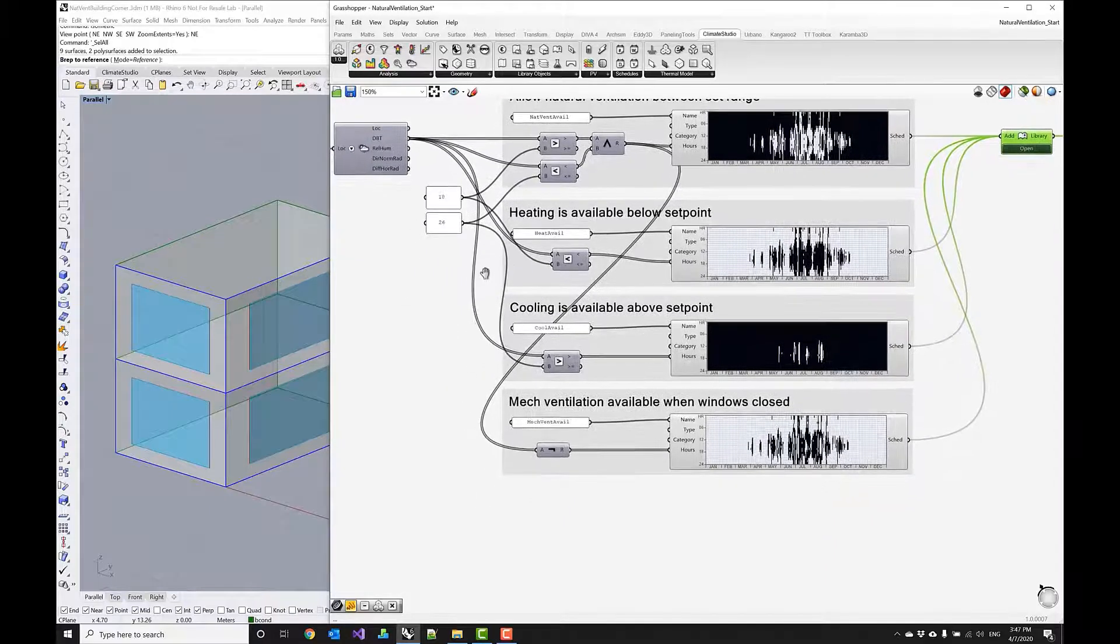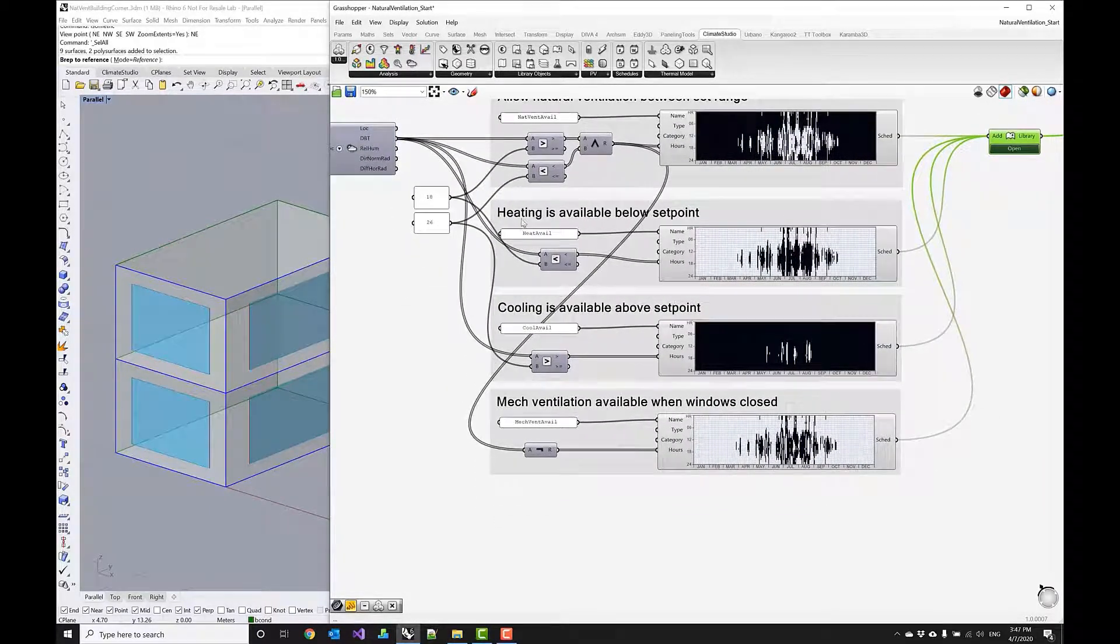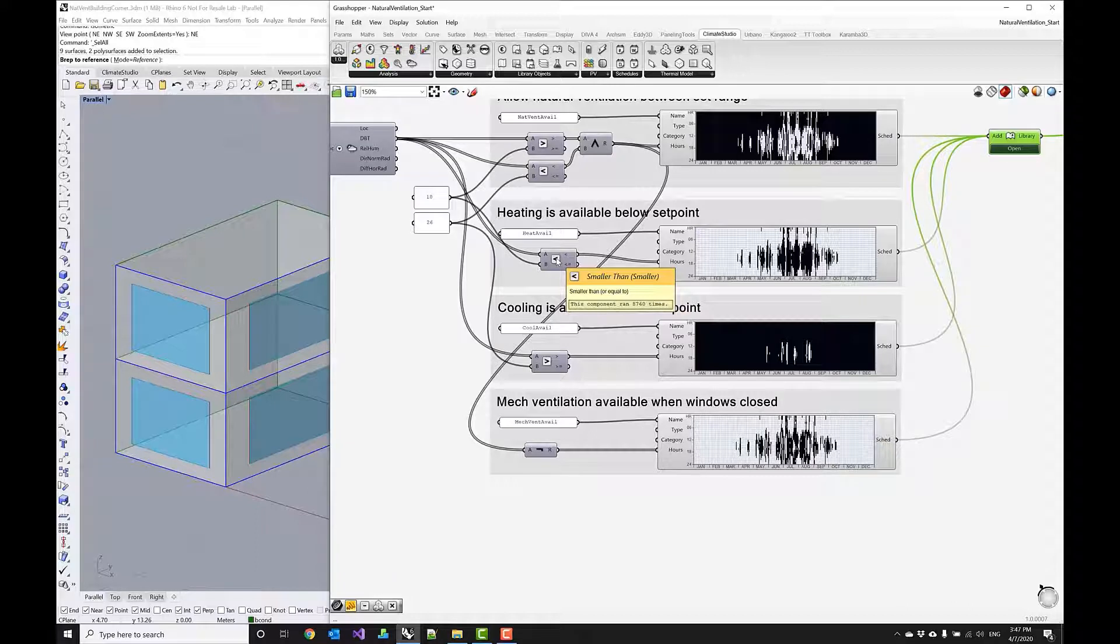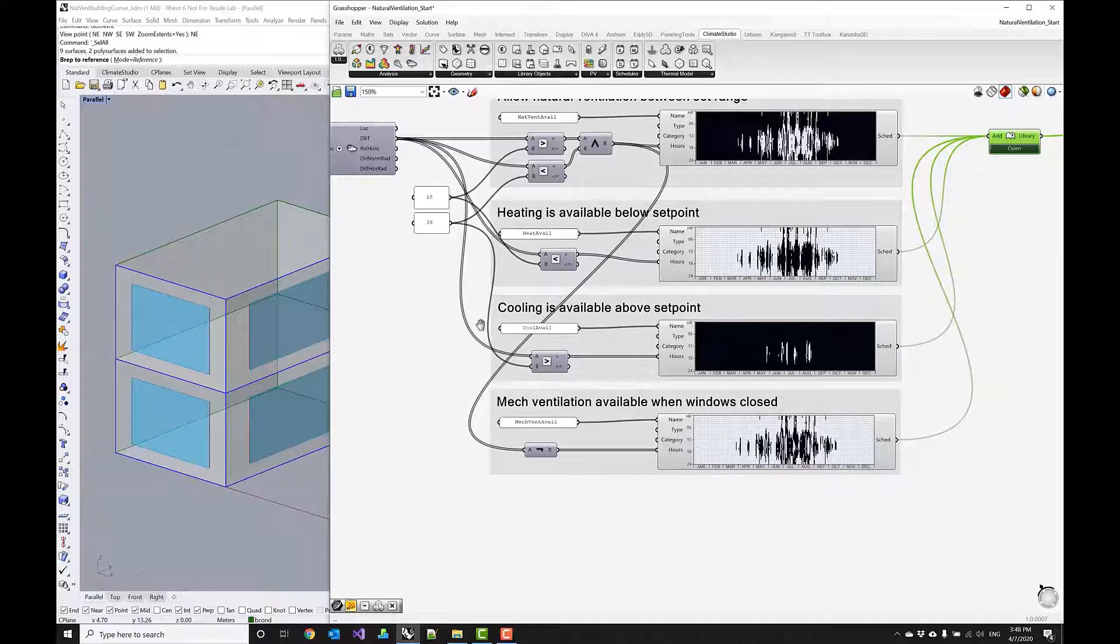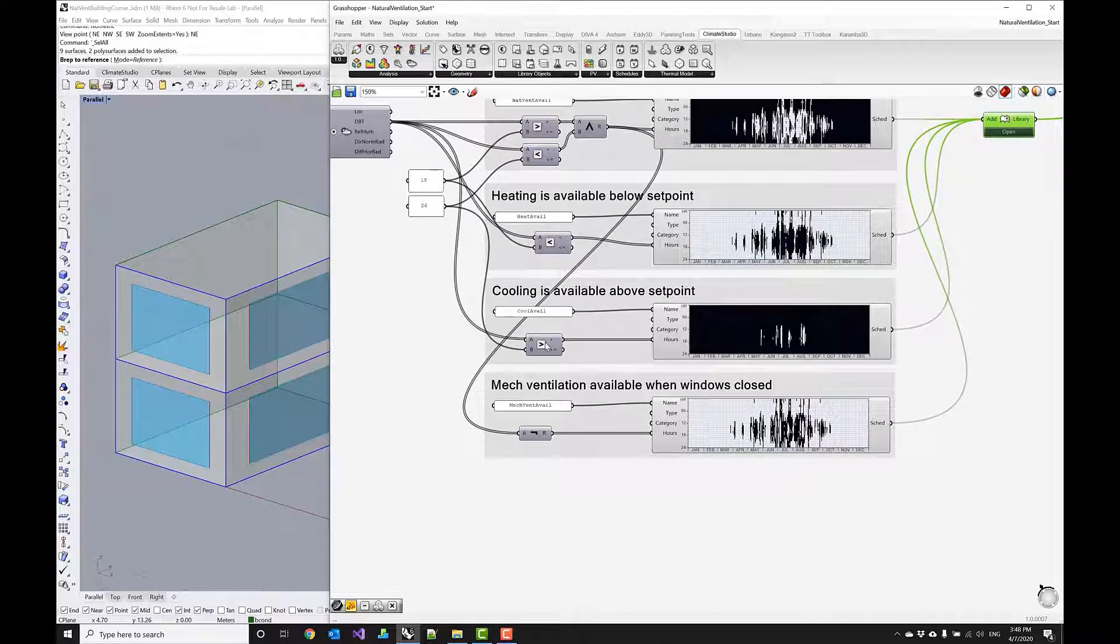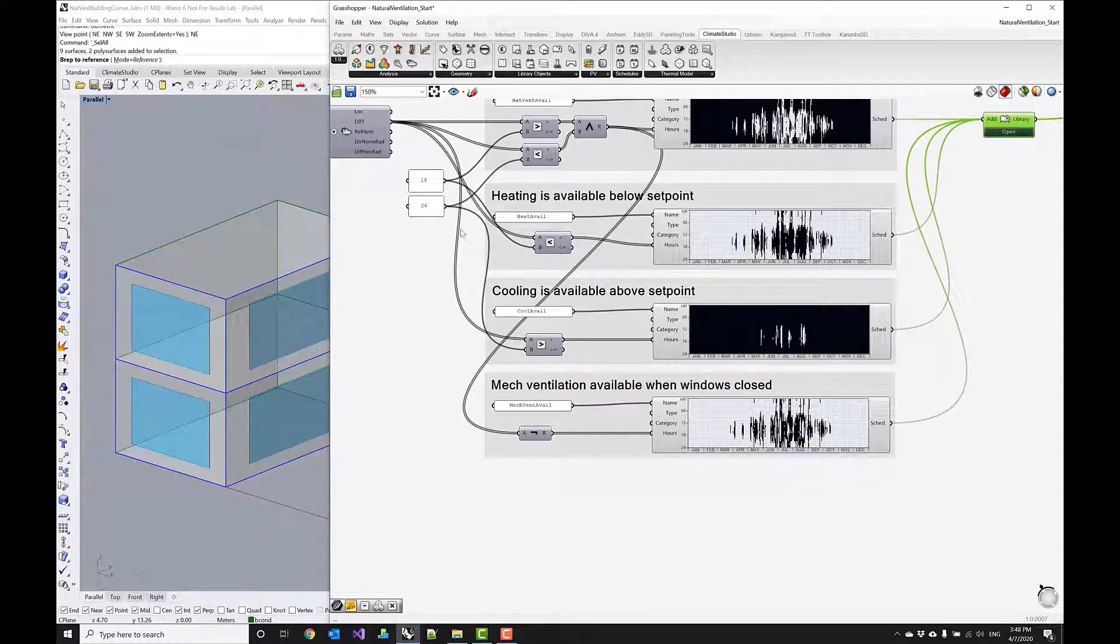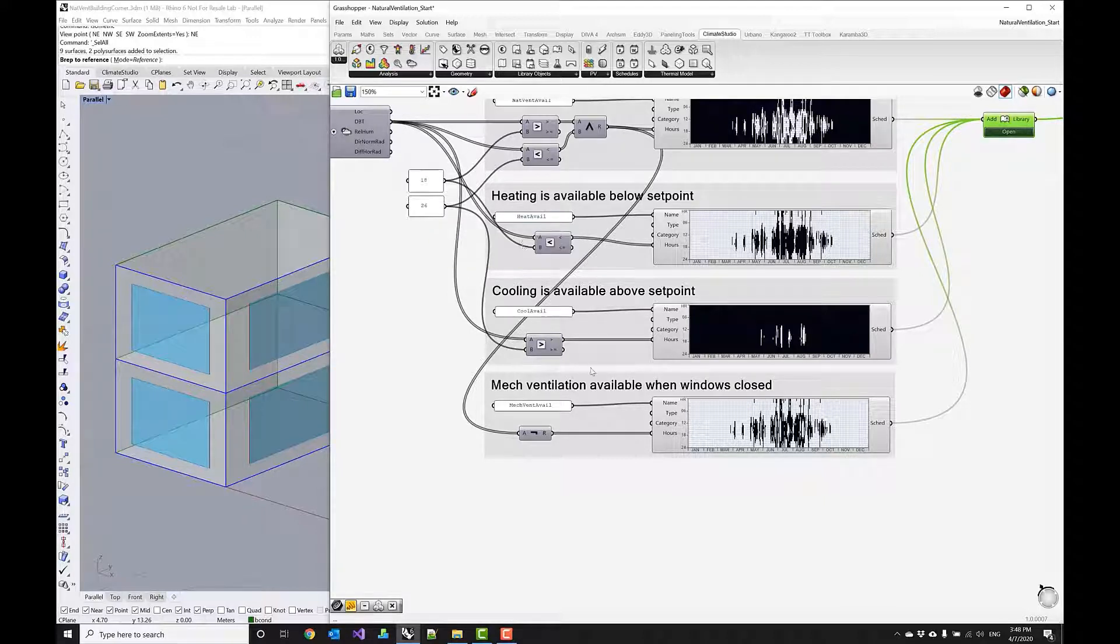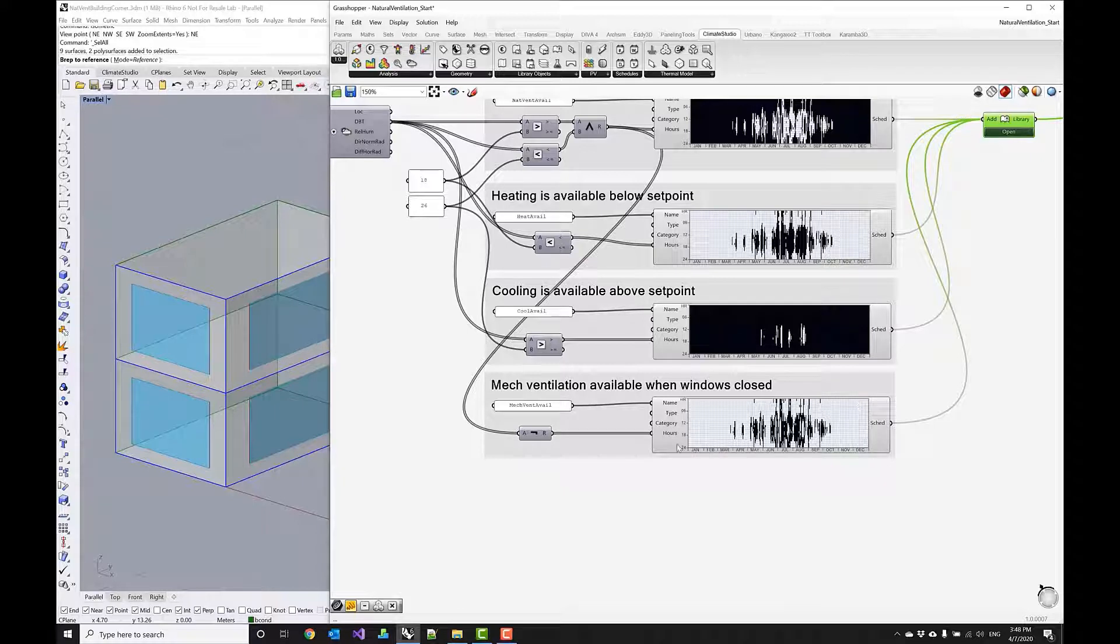And now I need to do the same for my heating so I have to make sure that the heating is scheduled as well. Now the control logic is a bit simpler it's just whenever it's smaller than 18 degrees C outside then I want my heating system to be available and this is the pattern that you would get from that.